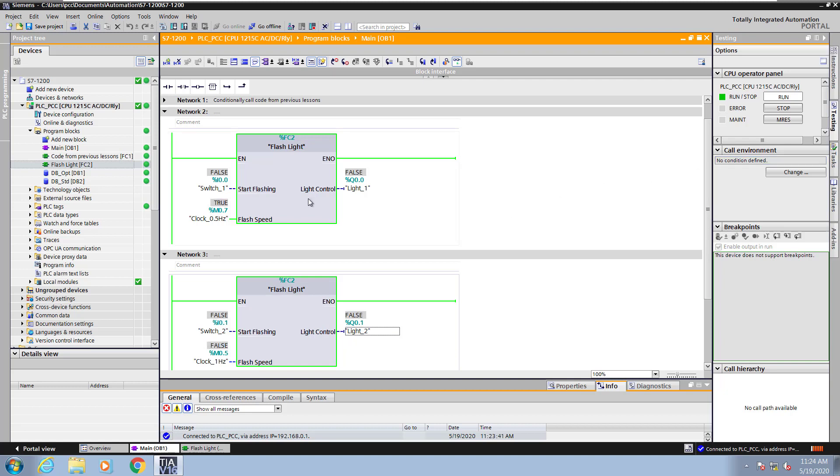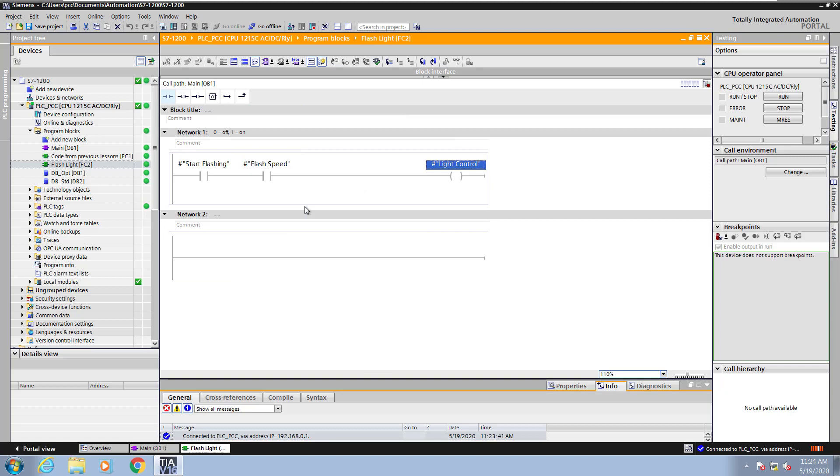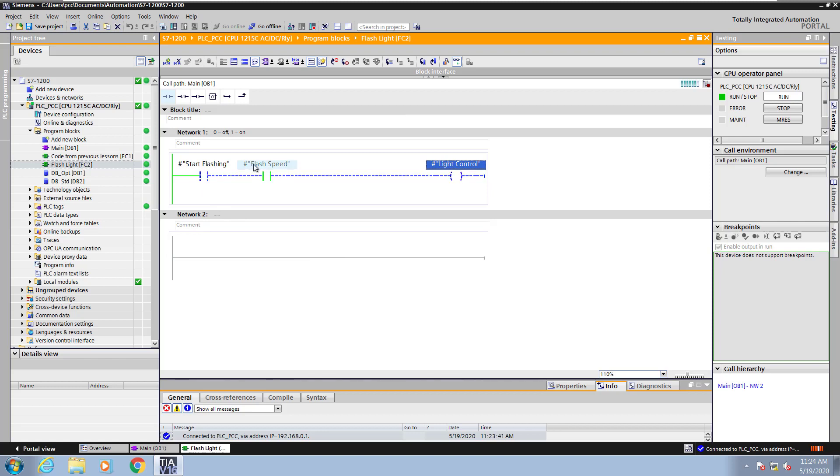I will set the call environment by right-clicking on FC2 and network 2 and selecting open and monitor. Now I can monitor the call to flashlight on network 2 in OB1. So I will turn switch 1 on which will start the light control flashing. I will turn switch 1 off and the light control will stop flashing.